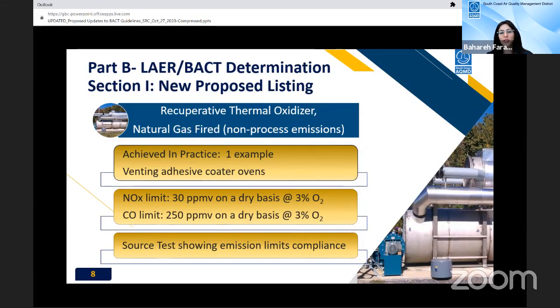The achieved-in-practice example is for a coating and curing facility with ovens that are directly vented to the recuperative thermal oxidizer. The source test data supports the NOx limit of 30 ppm and CO limit of 250 ppm corrected to 3% oxygen for a natural gas-fired burner. The equipment shall be maintained and operated at a minimum destruction efficiency of 95% and overall VOC efficiency of 95% according to the permit. The thermal oxidizer has been in operation for more than 2 years.